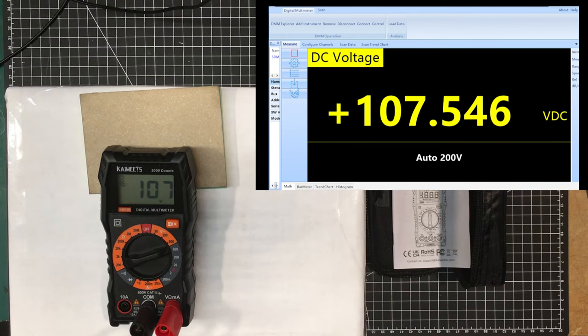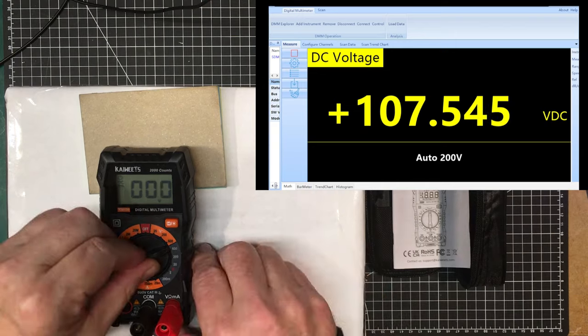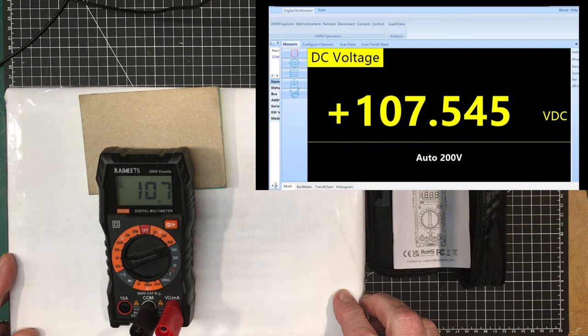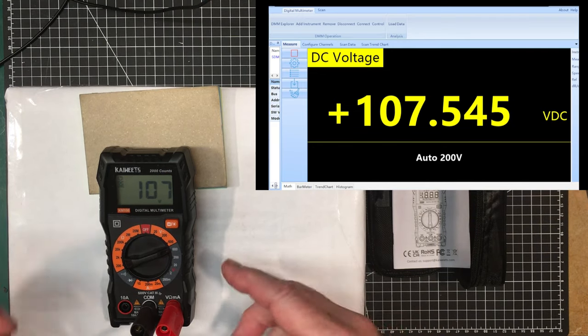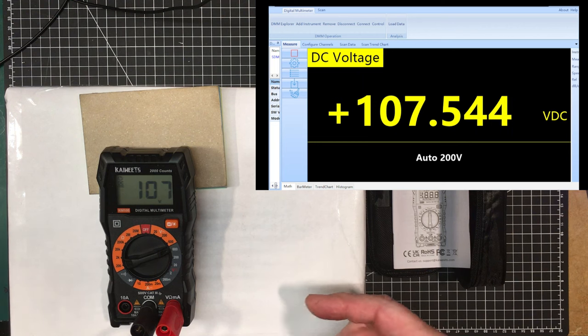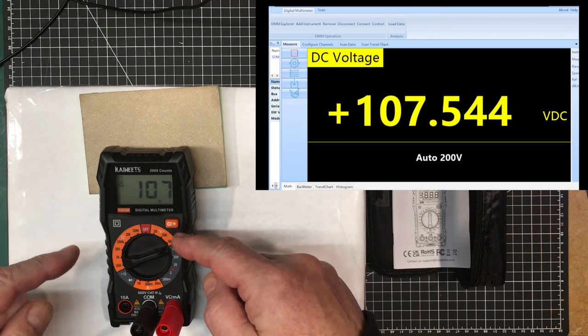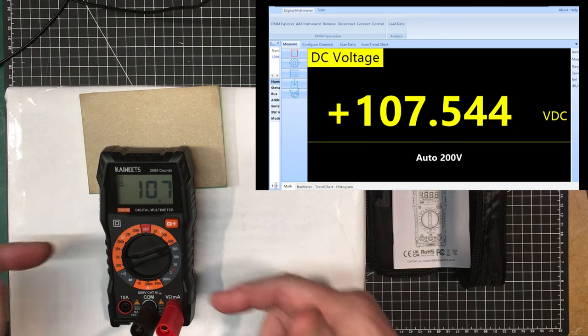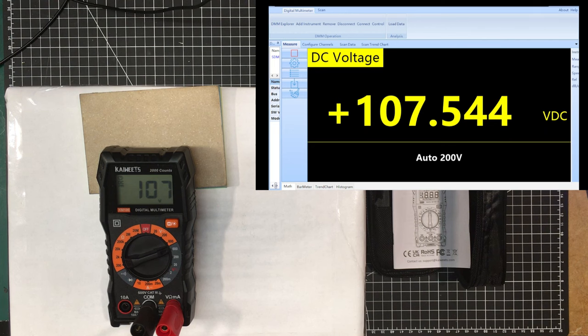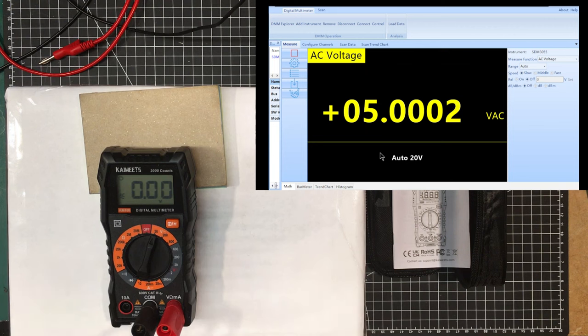We'll just verify it says the same thing up here on the 600 volt range and it does within the one percent. I'm just going to get a signal generator here, we're going to try some lower voltages on the AC side and then I'll just plug it into the mains to see what it gives us there. Let me set up for that, we're right back.